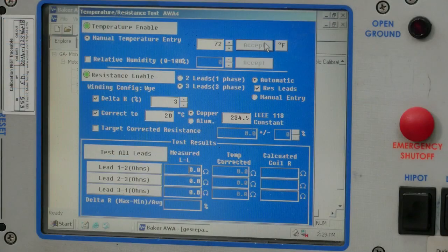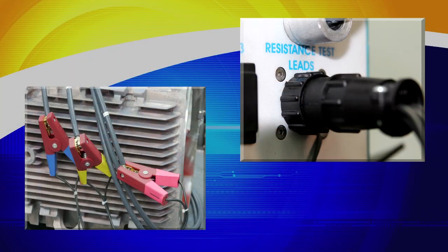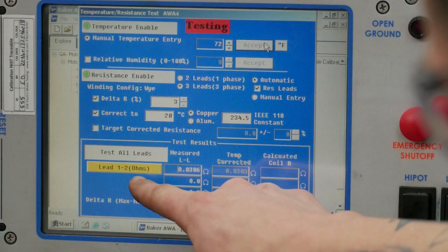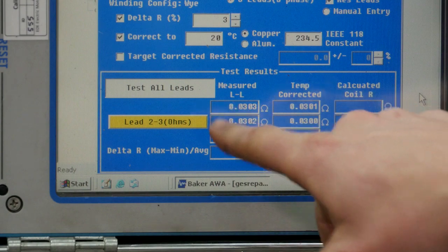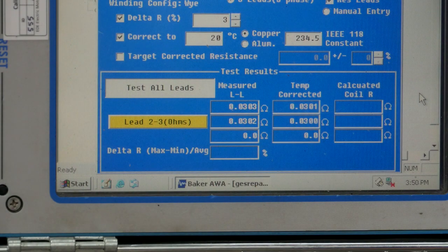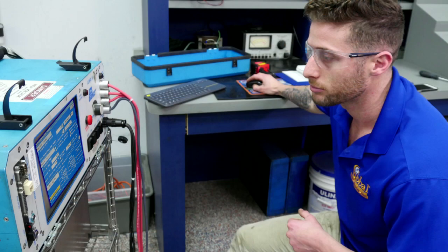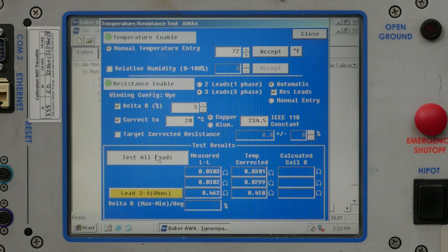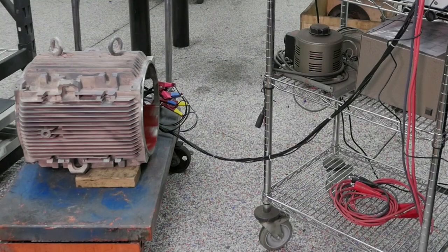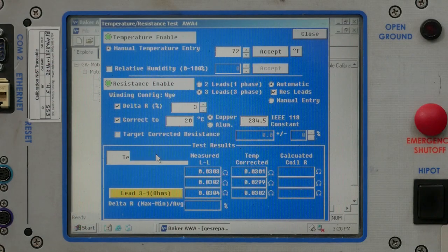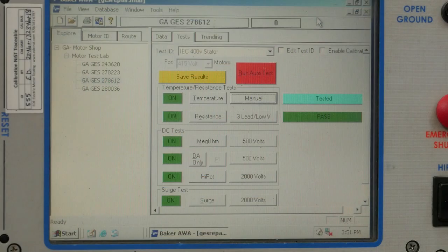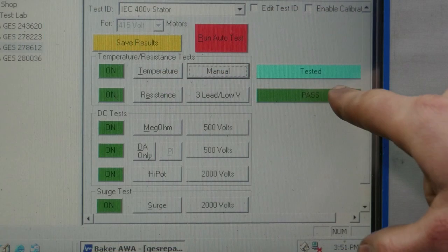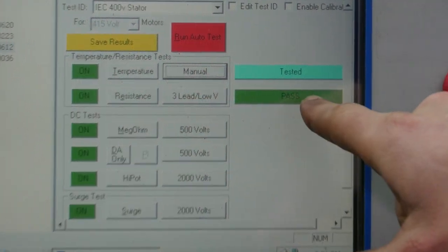The AWA will measure the ohms of each phase, first comparing leads 1 to 2, then leads 2 to 3, and finally leads 3 to 1. Here, we see the resistance test has passed. So far, so good.